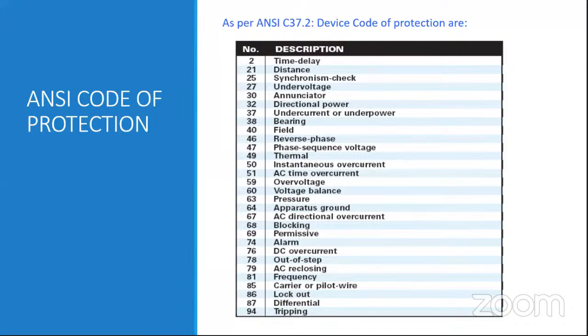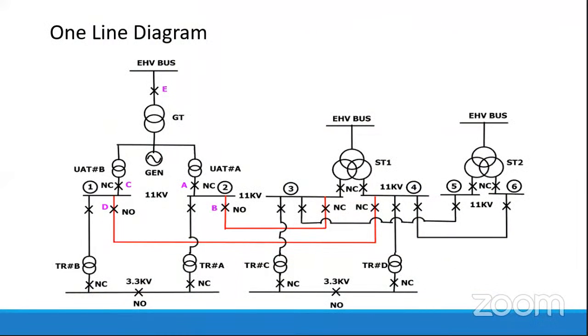The 32 is directional power. If there are two sources feeding the power, the protection should be given in a directional way such that no power feeds into the other source. If there is power from this grid and EHV bus, it should not feed this generator. Otherwise a fault condition occurs in the generator and the generator will get damaged. So we should provide directional protection that detects the direction of power or current, and gives a trip command if the direction is not fulfilled.